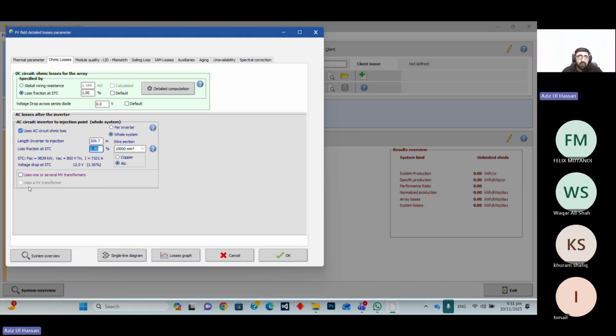Use one or several MV transformers, or HV transformers. If we are connecting our solar power plant at low voltage, we have to check our PR at the LV side of your transformer. Then you don't have to insert these options. But if your PR, the performance ratio, is checked after the MV stations, and the POC, the point of connection, is after the MV transformer or HV transformer, then you have to put that in your simulation, because there are also some losses in those options. But if you are doing your termination at the low voltage side, then you don't have to include these.